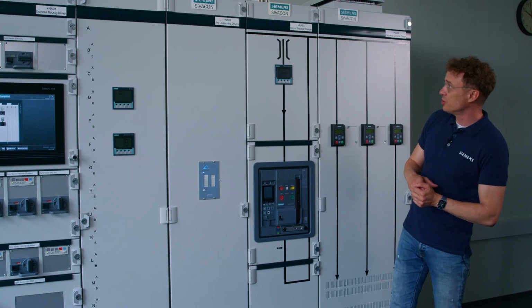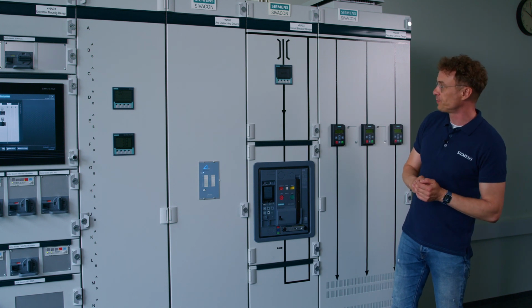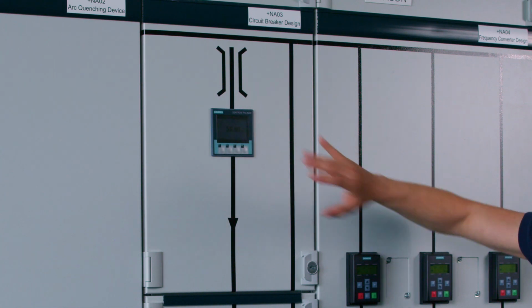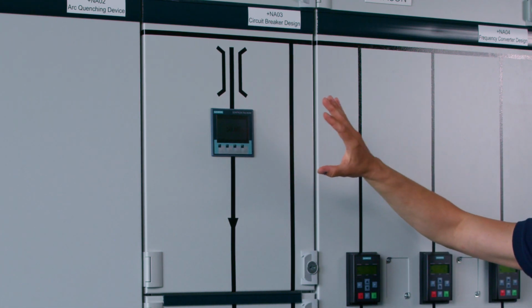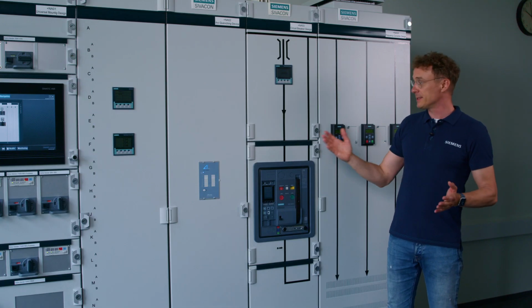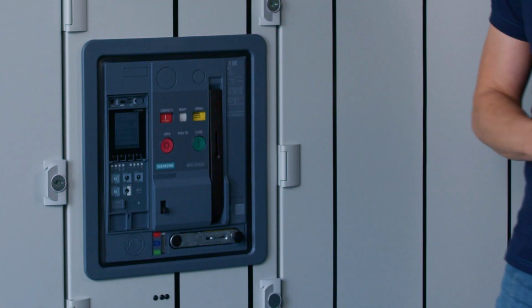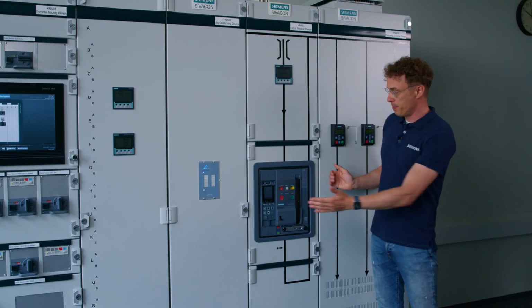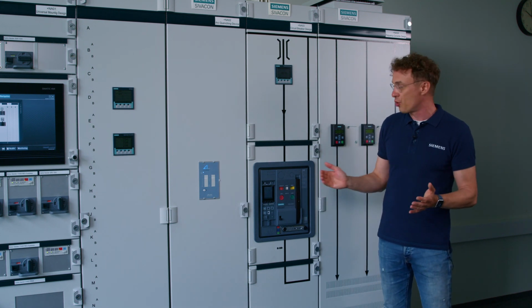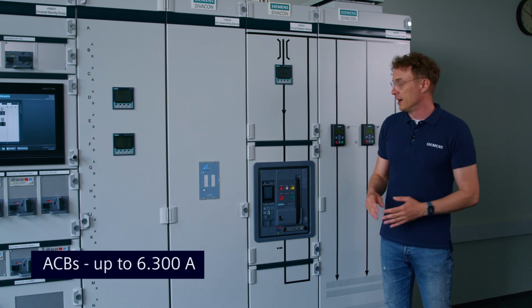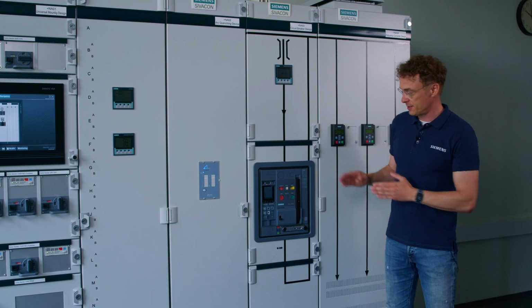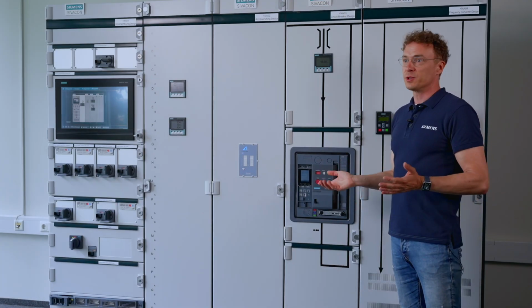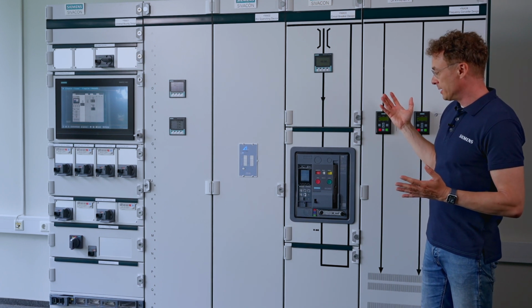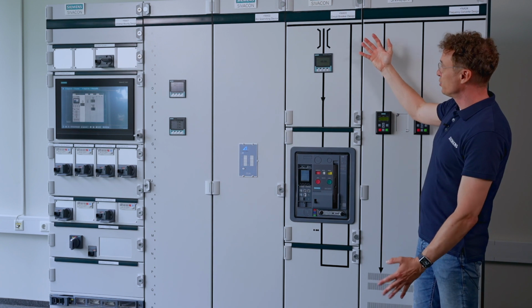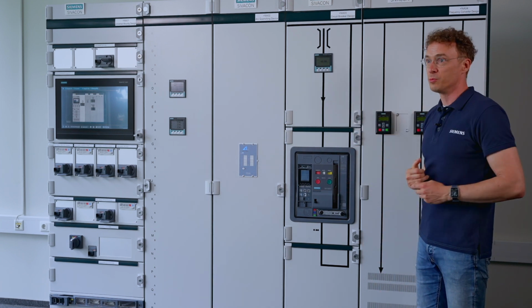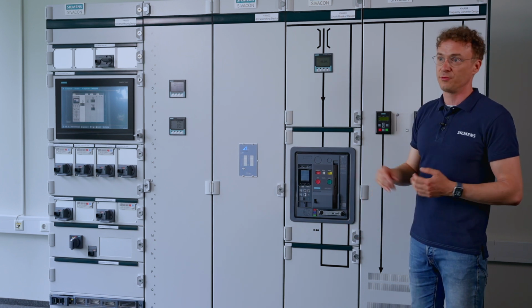There are three sections inside this cubicle. Up at the top location, we have the cable compartment, or in this case, the connection to the busbar trunking system, SIVACON S8 PLUS. In the middle, we have the main breaker, the 3WA. This is rated from 630 amps up to 6,300 amps, then in obviously bigger frame sizes than we have here. And the lower compartment is used for auxiliary circuitry. If the local installation requirements are different, you can also swap the locations of the upper and the lower compartment to have the infeed from below.